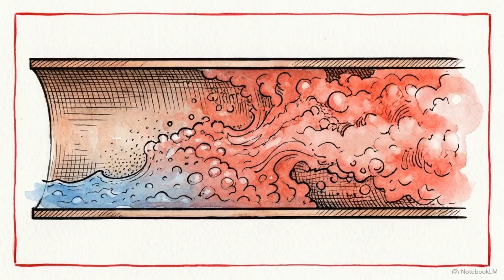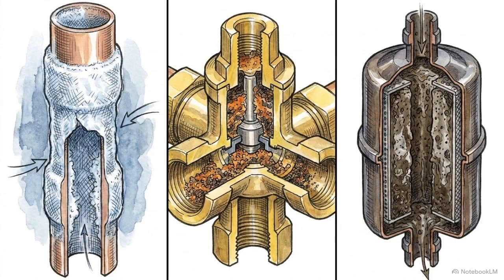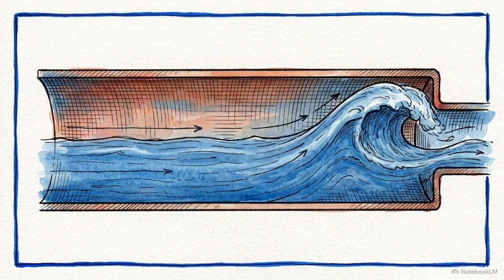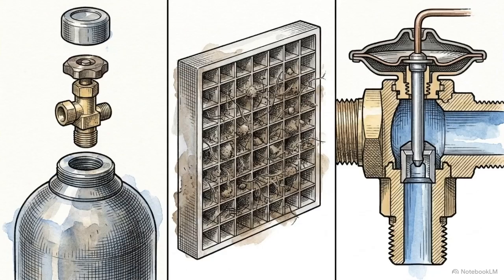If the actual superheat is higher than the target, the evaporator is starved. This indicates a low refrigerant charge, a restricted metering device, or a clogged filter dryer. If the actual superheat is lower than the target, the evaporator is overfed. You are looking at a system overcharge, poor airflow, or an overfeeding TXV.